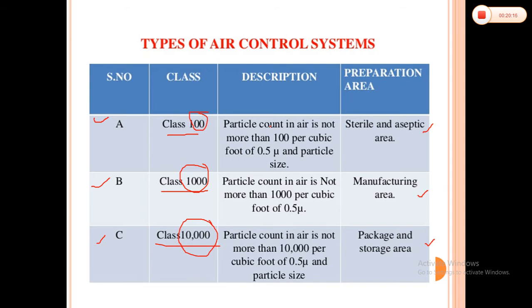We are using high efficiency particulate air, HEPA, filters, defined as at least 99.97% efficient in removing particles of 0.3 micron size and larger, composed of glass fibers, and filters of the electrostatic precipitator can also be employed. The air passing through these units can be rendered virtually free from foreign matter. Another air cleaning system washes the air with a disinfectant and controls the humidity at the same time.